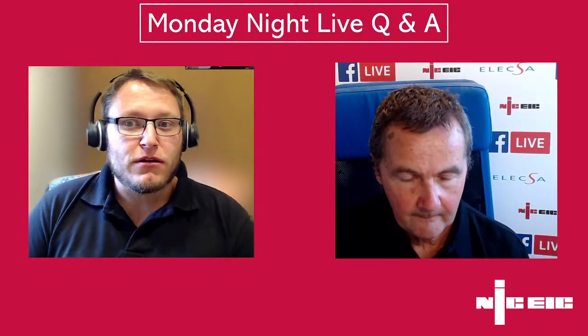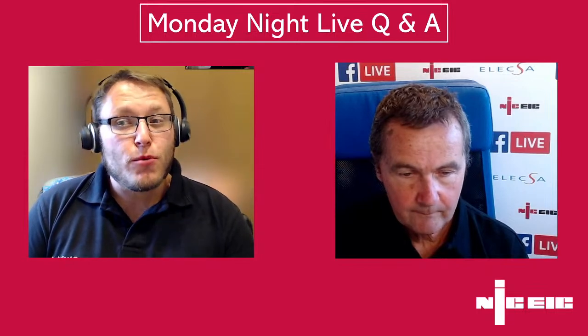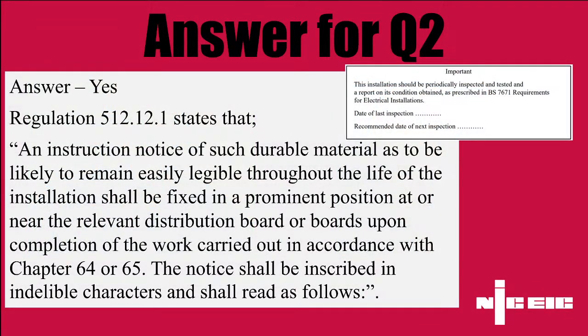And it does state there, an instruction notice of such durable material as to be likely to remain easily legible throughout the life of the installation shall be fixed in a prominent position at or near the relevant distribution board or boards upon completion of works carried out in accordance with chapters 64 and 65, 64 being for initial verification and 65 being for periodic inspection and testing.